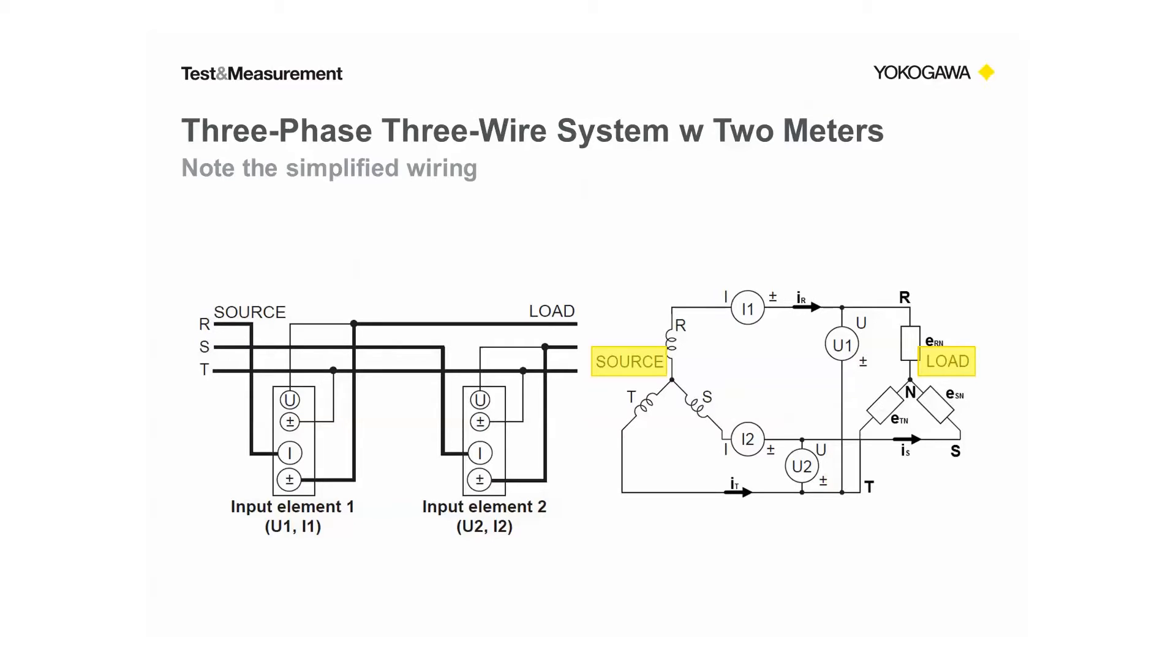Only two phases pass through the current inputs of the power meter on each of the two wattmeters. The third phase, phase T, is uninterrupted. There is no ammeter on it. You can see that we are measuring two voltages and two currents. That is to say that we have two wattmeters.